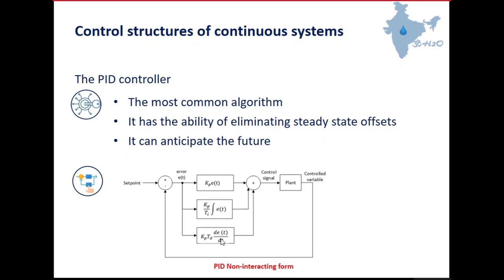There is also a derivative block, multiplied by a parameter called the derivative time. These three blocks can be calculated in parallel — this is the non-interactive form of the PID, where the three blocks are calculated in parallel and summed to evaluate the control signal. You can find different ways of combining the actions. One important thing is that actuators have limitations — for example, a valve can be fully open or fully closed, or a pump has limited speed.